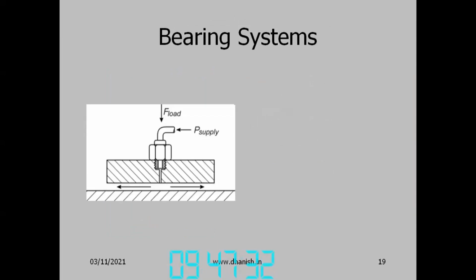Then the bearing system. Most commonly nowadays we have only air bearings, pneumatic bearings. So air bearings consist of a circular disc through the center of which air at pressure, so P supply is air at a pressure, is delivered to the center of the hole, and from the bottom it escapes through all the sides. So this whole disc is supported on a thin cushion of air, so it is able to withstand a load, F load. So the higher the pressure, it can withstand much higher loads. So this is the air bearing system.